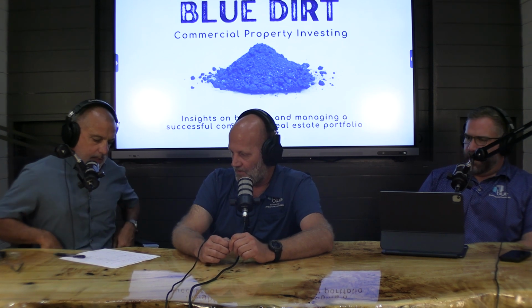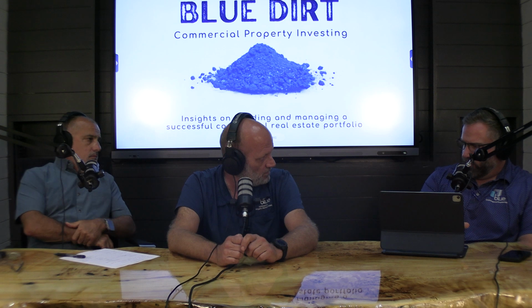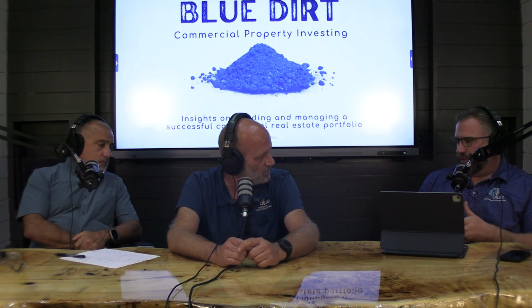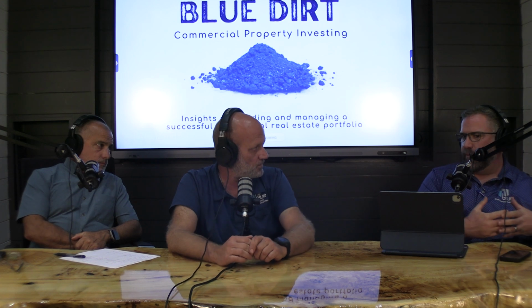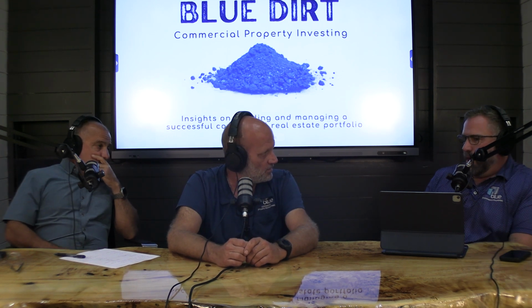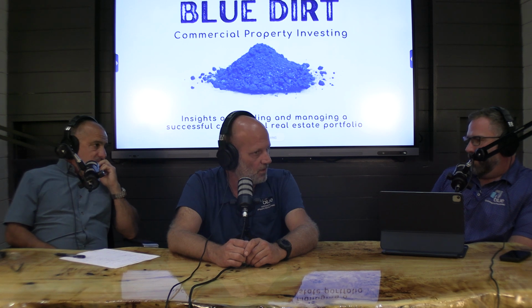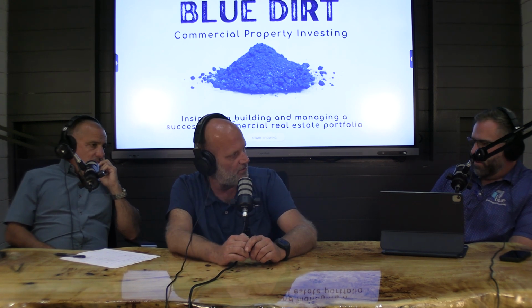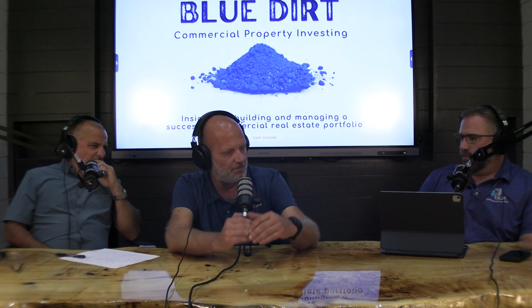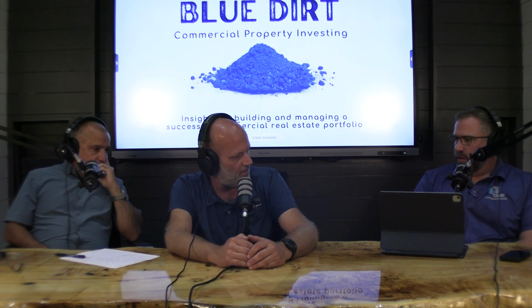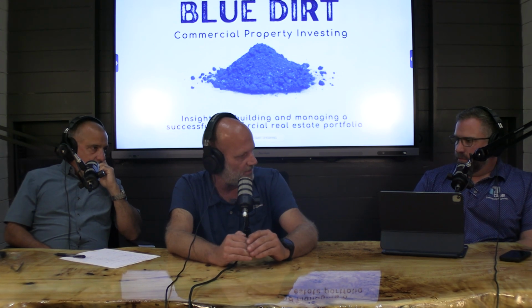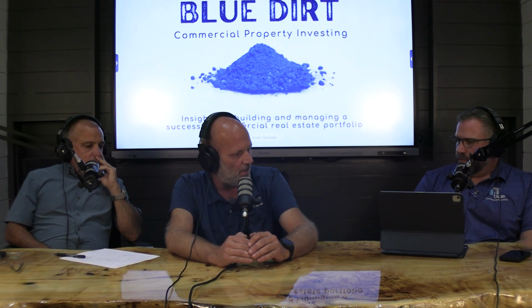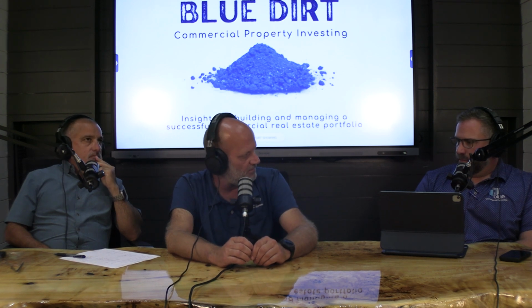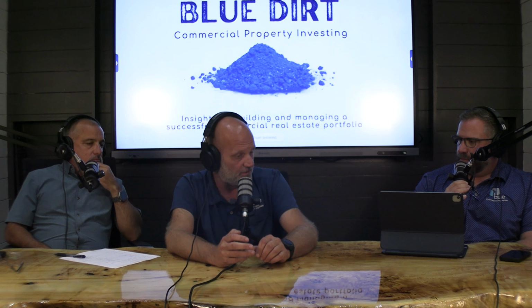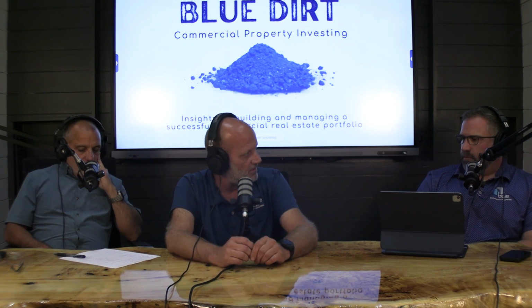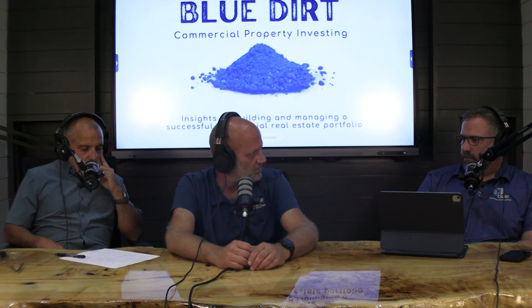So, okay. Now, you said that you would obviously be checking the drain pan, the other thing. What about filters, right? Because when I first started, I always thought that the filters were really just for air quality. Well, the air filter keeps all that dirt and whatever's in the air from getting up inside the evaporator coil. So if that evaporator coil gets clogged, it doesn't get the airflow through it. I'm sure most of us have probably seen an AC system that's iced up. A dirty filter can cause that. A dirty evaporator coil can cause that if it's clogged. And if it's low on refrigerant, it can freeze.